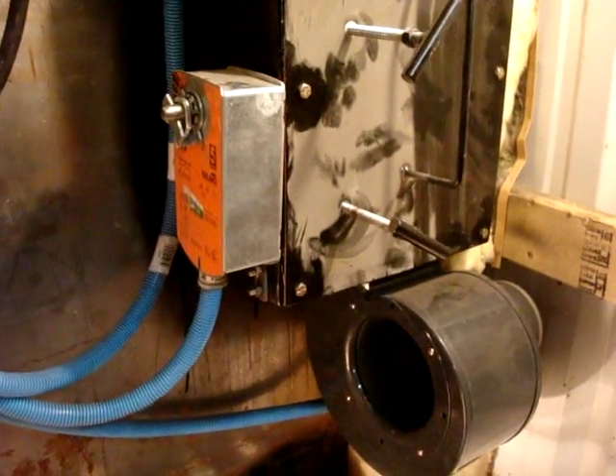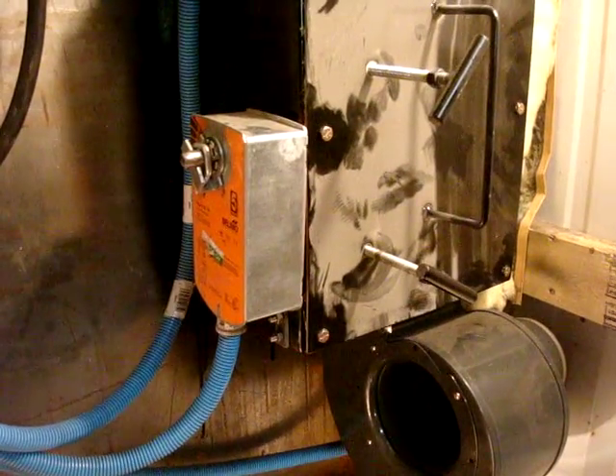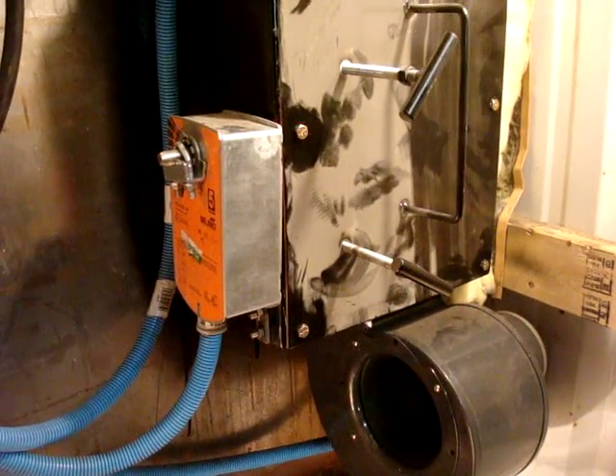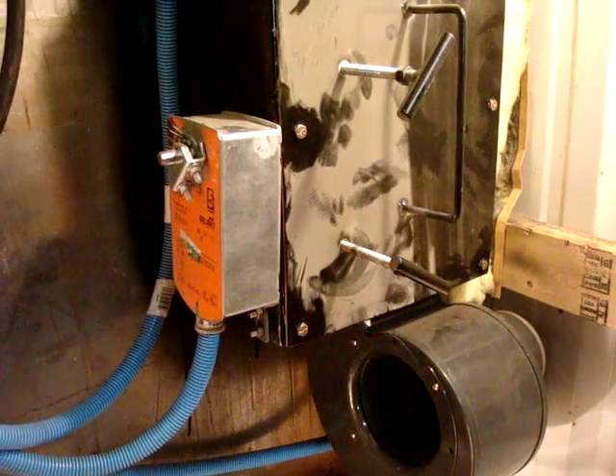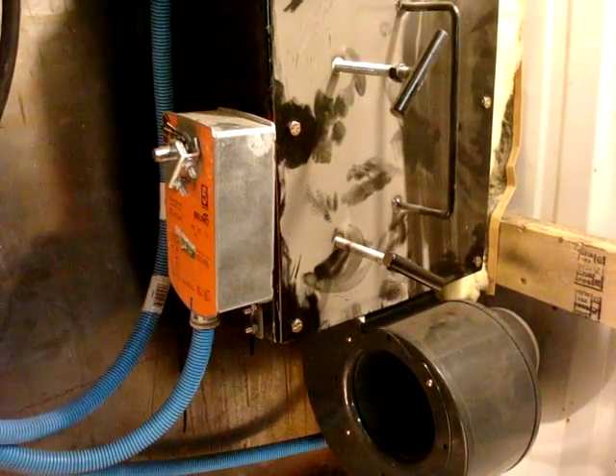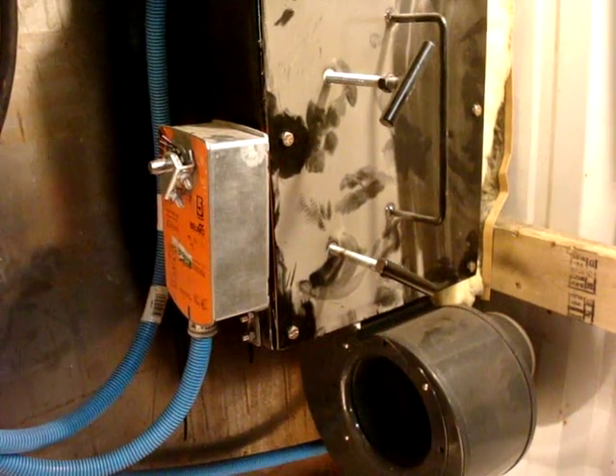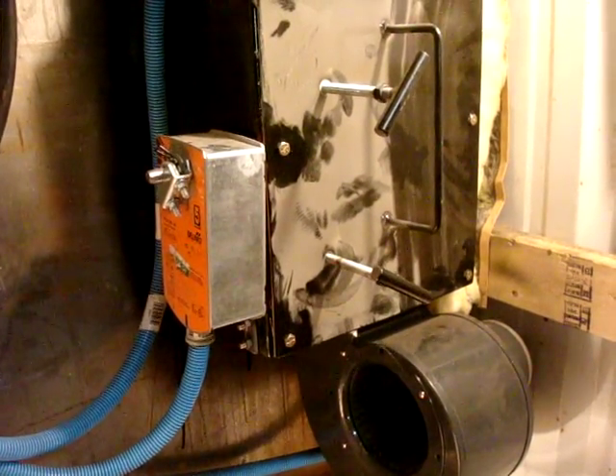You can see the panel shut off and then the damper will close on its own. This damper is spring-return — it doesn't require any power to close. It's power-open, holds open, and spring-returns to close. So if there is a power failure for any reason, that damper will close and shut all air off to the furnace, so I have no runaway conditions or boil-overs.